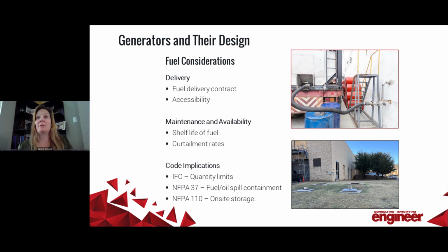But regardless of whether it's above ground or below ground, you really need to consider the path for the fuel delivery. So the tank has to be accessible by a fuel truck, right? Sometimes you may be forced to put that tank in a fairly inaccessible location, which is okay. It's not great, but it's okay because they do offer remote fill stations. Of course, there's piping associated with it, but it is an option.